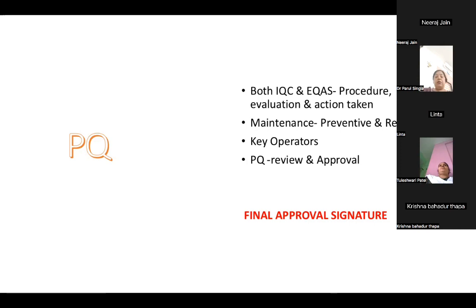Then maintenance: what all is required, what is the schedule of preventive maintenance, whether you will be doing 6 monthly major maintenance or yearly maintenance. Then calibration schedule, you will be doing it yearly. Then repairs: any time there is a fault in the equipment, a repair mechanism will be undertaken, whether the personnel in the lab will be trained for major troubleshooting, or a company engineer has to be asked. So key operators should be identified.